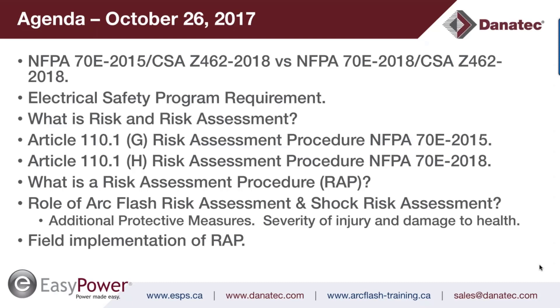I'll emphasize again that the risk assessment procedure is misunderstood in industry, and I'll discuss the role of the arc flash risk assessment and the shock risk assessment — both mandatory requirements within your electrical safety program. There have been significant updates to those articles in the 2018 editions, particularly a material change to the arc flash risk assessment clause and to the arc flash PPE category tables, which in previous editions was called the hazard category table method.